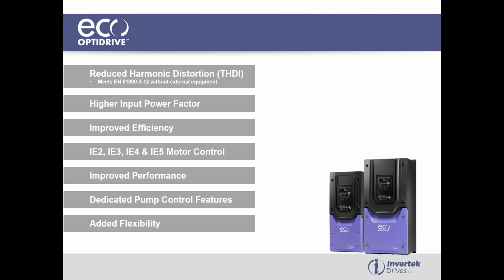And that covers VFDs with phase currents of between 16 and 75 amps. So we have the declaration of conformity available, so you can just download that if you need it for project documentation, for example. We also run with a higher input power factor, so that helps to improve the efficiency of the overall system.